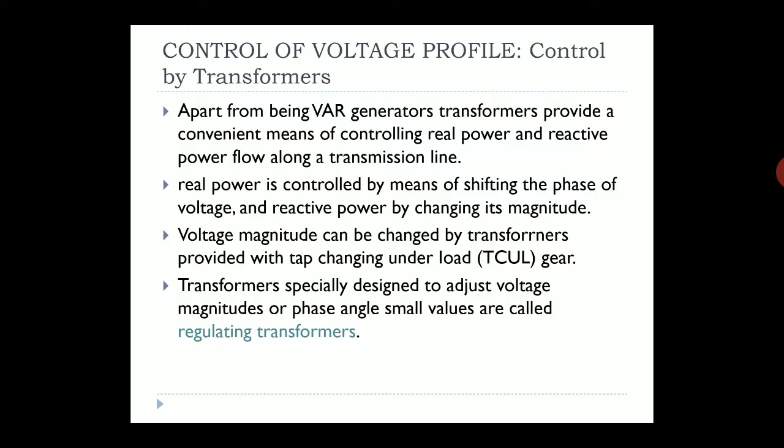Apart from being a VAR generator, transformers provide a convenient means of controlling real power and reactive power flow along the transmission line. The real power is controlled by means of shifting the phase — that is, the angle — of the voltage, and the reactive power is controlled by changing the voltage magnitude.